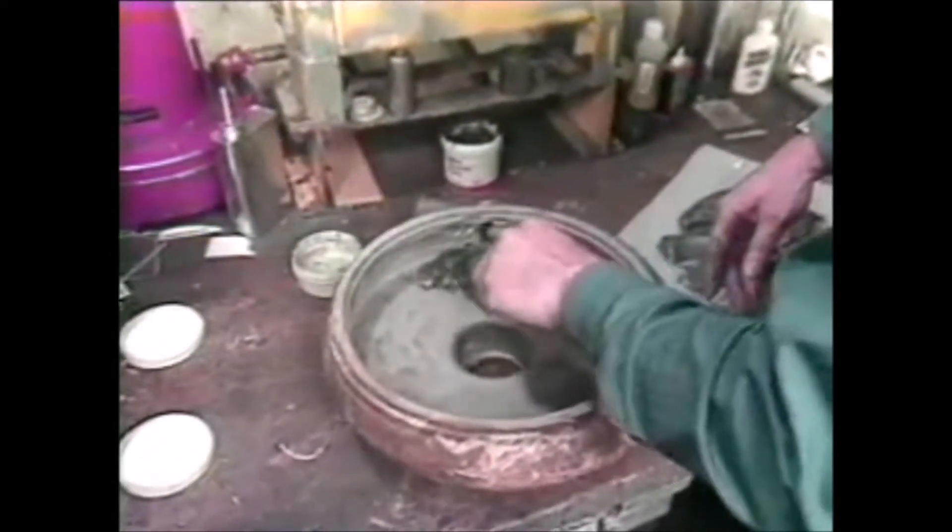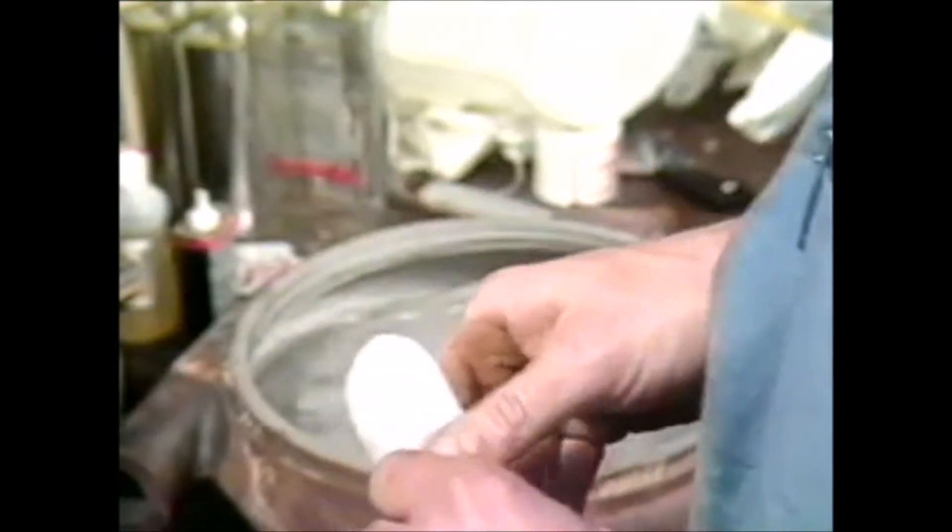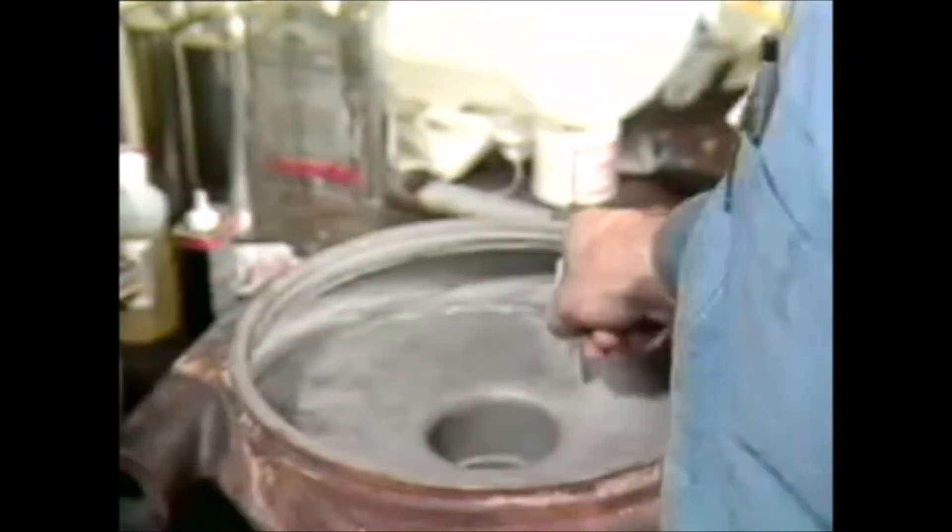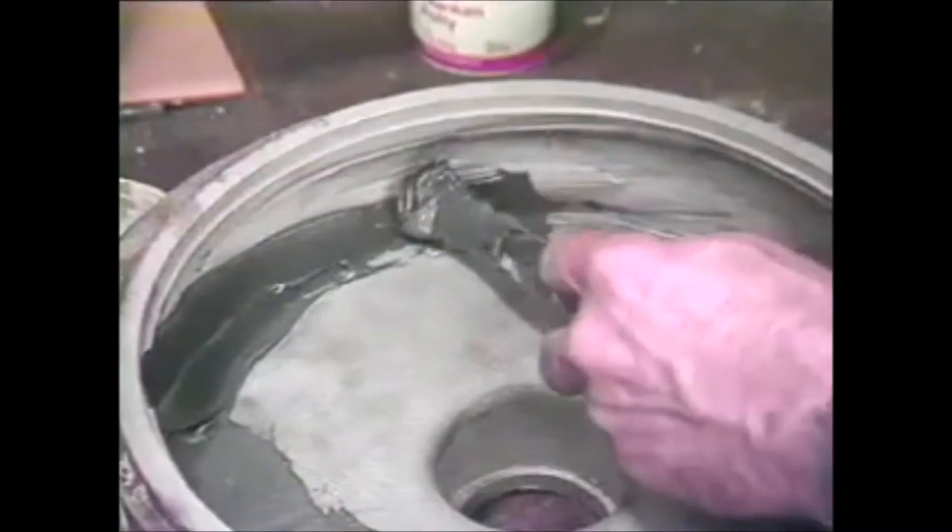The plastic applicator can be modified to assist in the application of the titanium putty on curved surfaces and in hard-to-reach areas. Apply the titanium putty to rebuild worn areas to equal original equipment dimensions, allowing for proper clearance of the impeller.